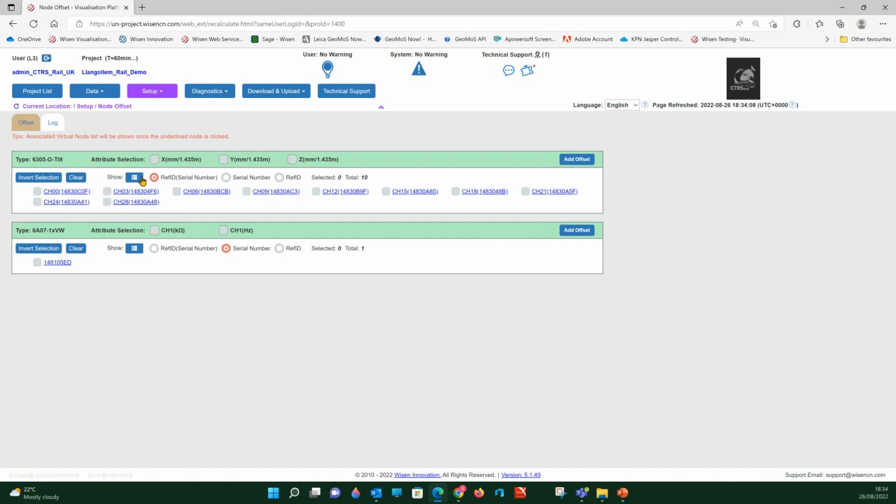Now the node offset is a lot more powerful because obviously you're seeing the data graphically. You can set a median or an average, whereas within the railway model it is a very specific point, so that is not an average or a median value. So if your baseline, your commission period is short, then in essence it's kind of irrelevant in terms of setting an average or a median, but you want to make sure you haven't got an outlier, that you're not at the peak or the trough.